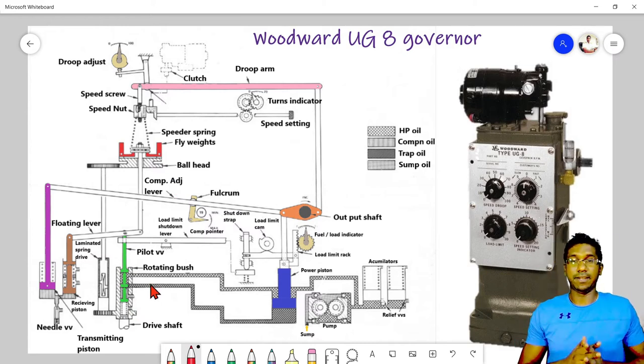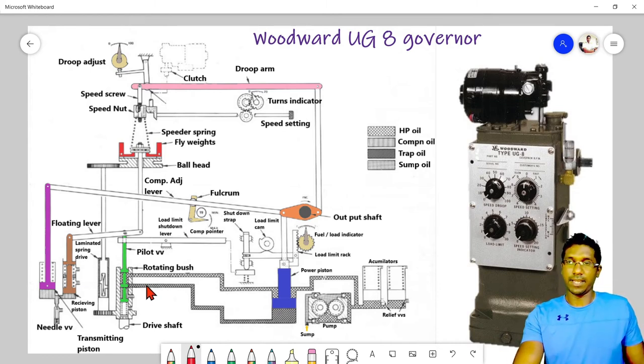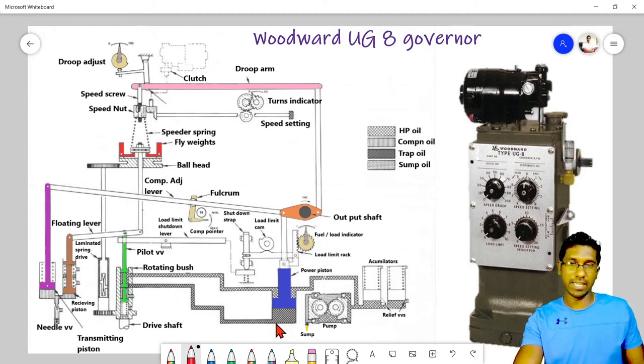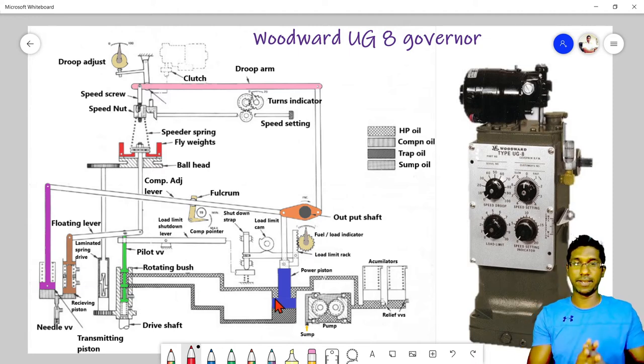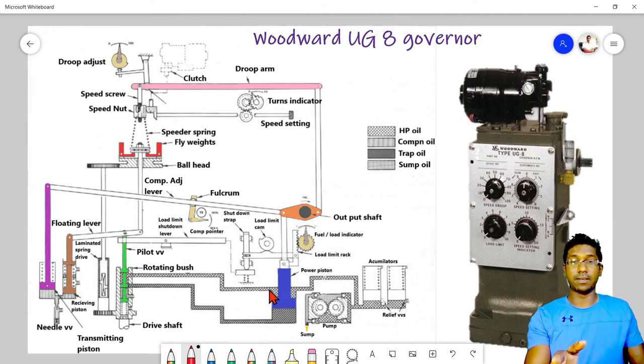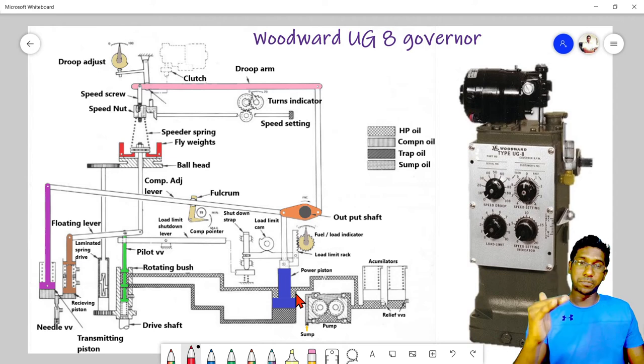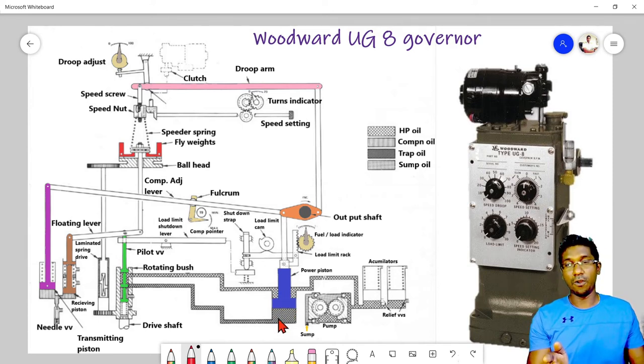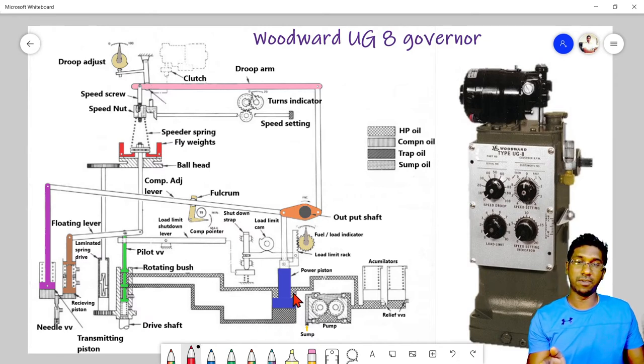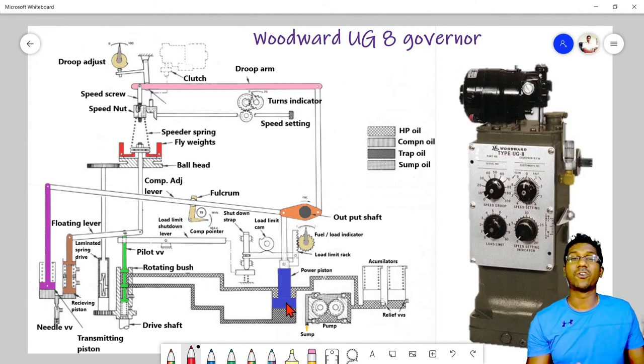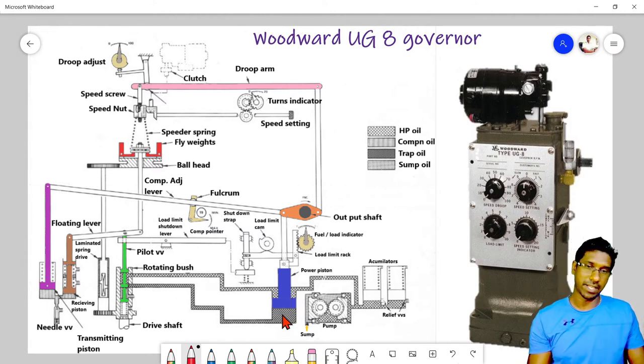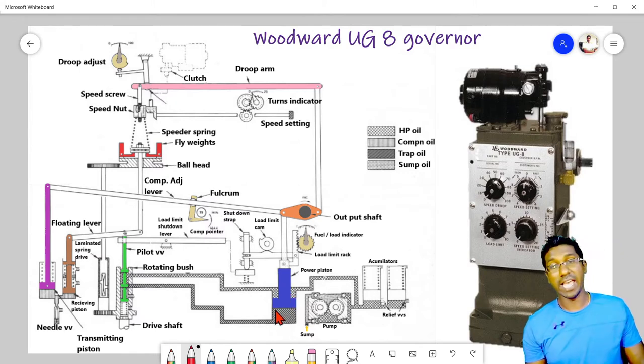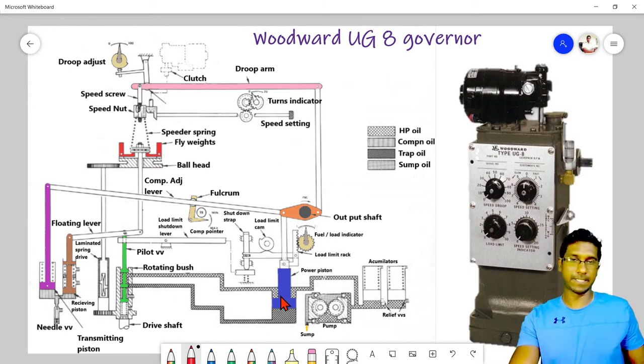By maintaining minimum friction through the rotating bush and pilot valve arrangement, the dead band is kept at a minimum value. Looking at the power piston: there is a difference from previous discussions — instead of a mechanical spring, hydraulic oil pressure provides the spring action. Due to the cross-sectional area difference, the bottom part of the piston has more area than the top. Therefore, with equal pressure on both sides, the net force is always upward, always pushing the piston upward.